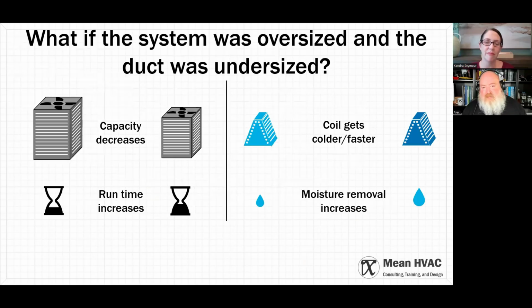We talked about this in the load calculation episode, so go back and watch that. The fact that many people have undersized ductwork is actually the only reason their system currently works. Modern blowers are often designed to overcome the problems of undersized ductwork, which solves that problem but creates another—it's a whack-a-mole situation. Great, you have better airflow, but now your system is oversized and you're miserable because you're not comfortable anymore.